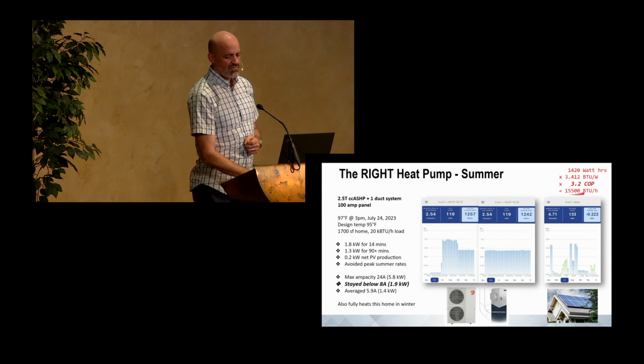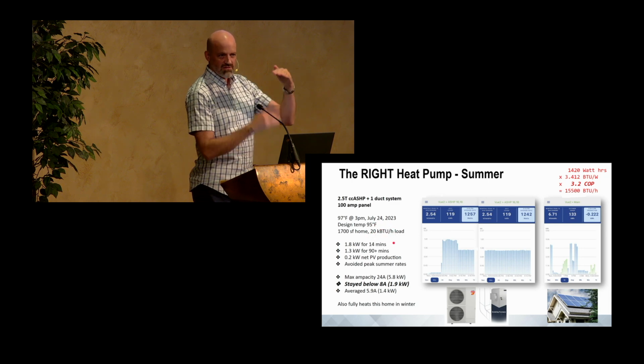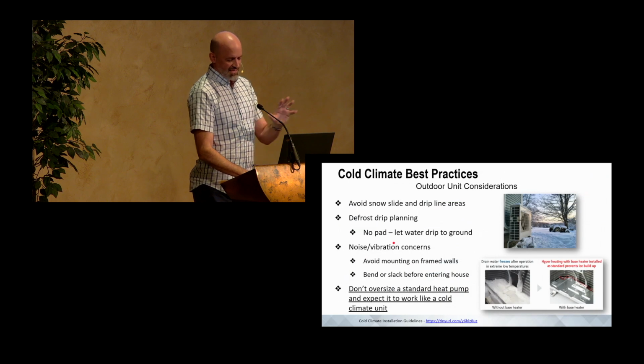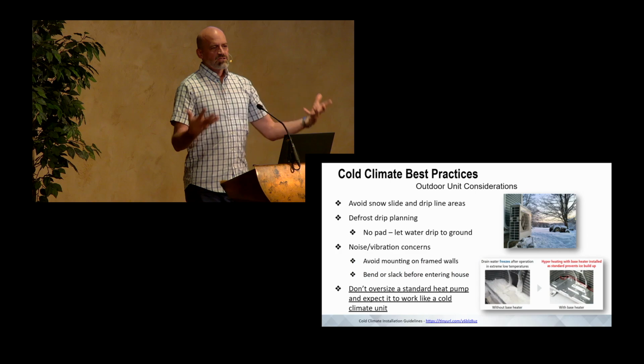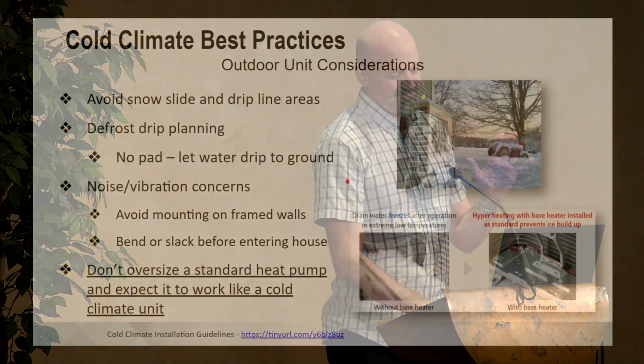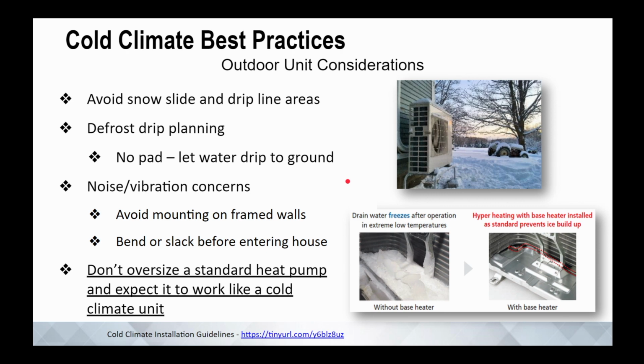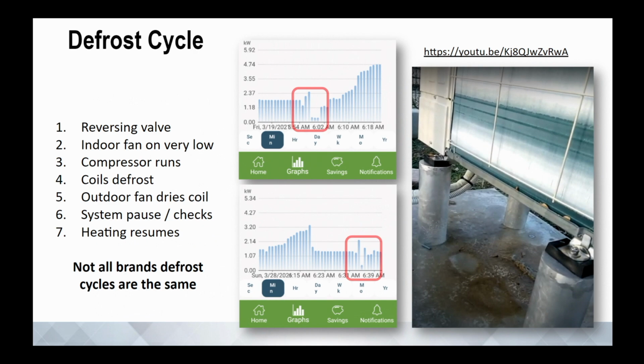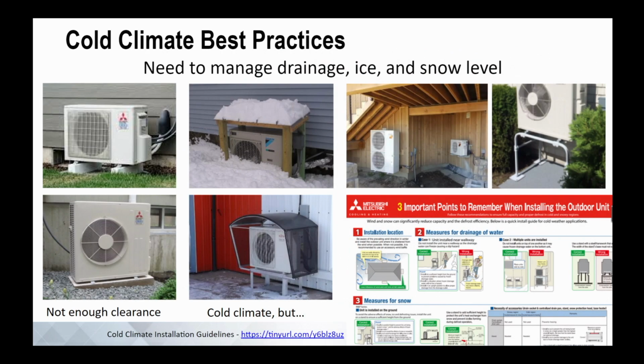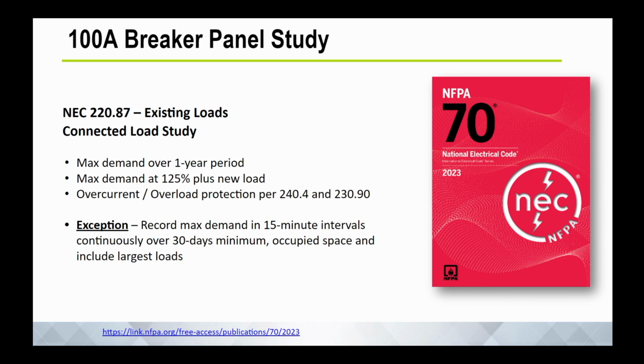And here's the other big question mark. 1,600 BTUs on a house that's designed at a heat load calculation, cooling load calculation of 20,000. So there's this disparity. We can get into that in the Q&A. So that's some field data, right, on operation of the heat pumps from one perspective. And so just some goals. Actually, do you want to know about how to sort of plan around heat pumps and where to locate them? We can get to that later maybe. Is that all right? We'll keep rolling. All right. We'll come back to those. Defrost cycle. It's kind of fun. We'll come back to that as well. That's sort of outdoor unit location.